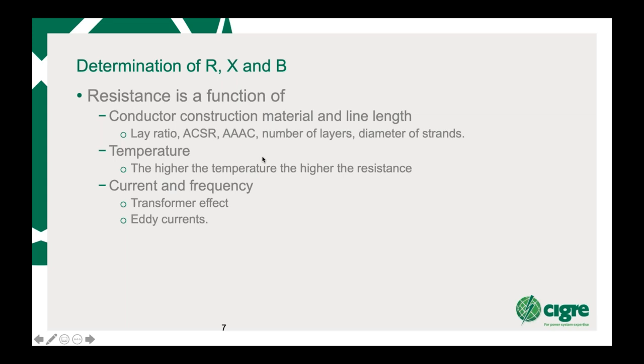And there's a formula which was covered in the last tutorial on that. Then we also dealt with this in the last tutorial or webinar. With current and frequency, you get a transformer effect and eddy currents with the swirling of the current around the steel core, which increases heat within the steel core, which will increase the resistance of the particular conductor. And this is all covered in an e-CIGRE brochure on AC resistance, whereby you can actually calculate the AC resistance of a conductor relating to frequency and current.